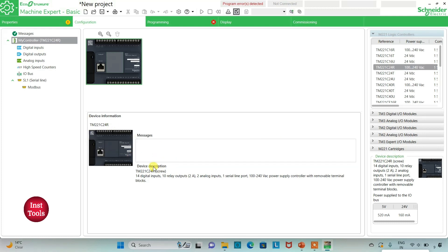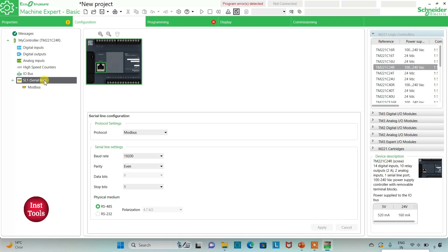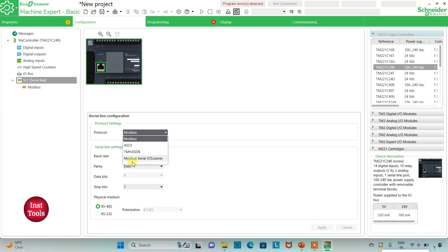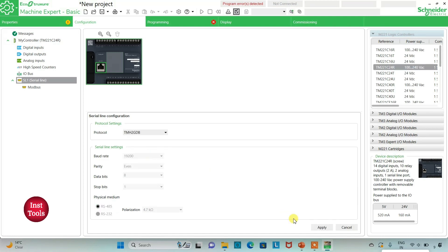The TM221 C24R has 14 digital inputs, 10 relay outputs, 2 analog inputs, 1 serial line port, and a 100 to 240 volt AC power supply with removable terminal blocks. I will go to the Serial Line settings and select the protocol as TM2GDB. I will keep it as TM2GDB and click Apply — with this protocol there is no need to set additional serial line settings.